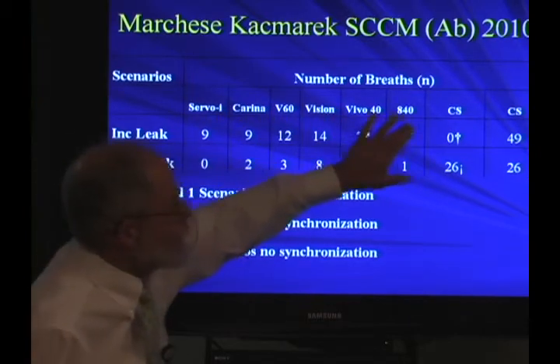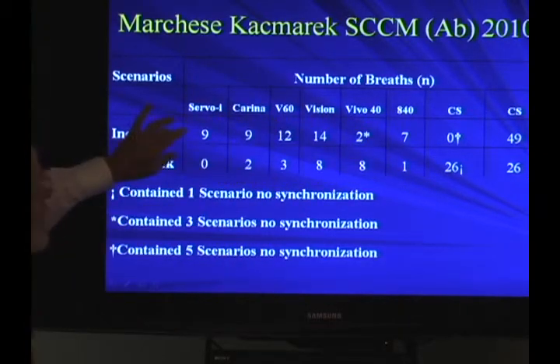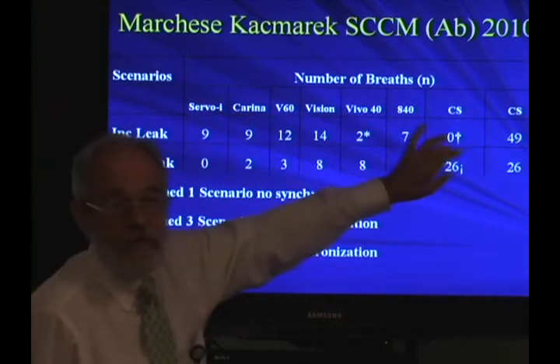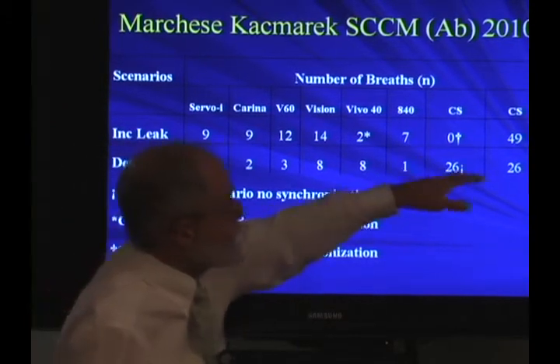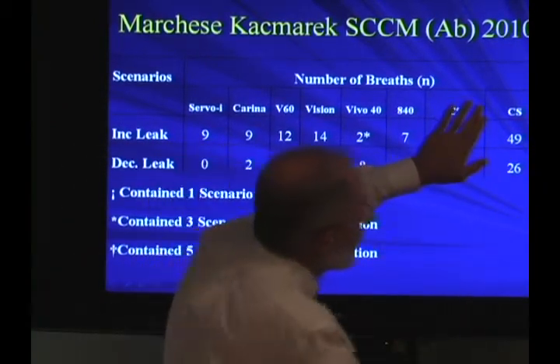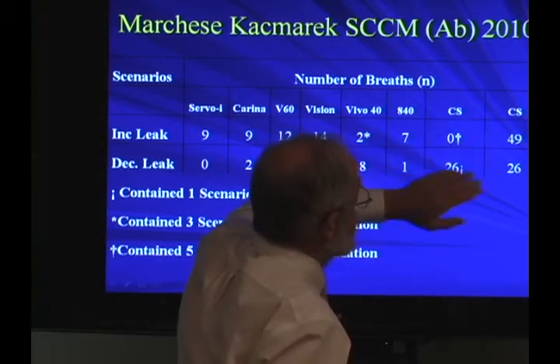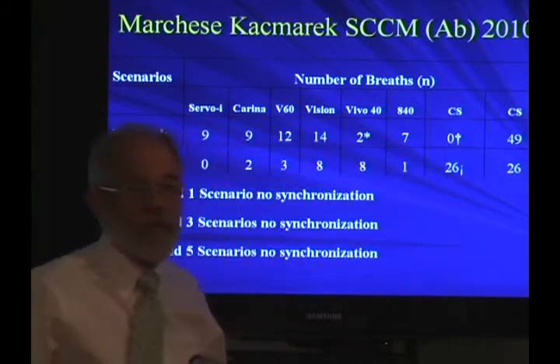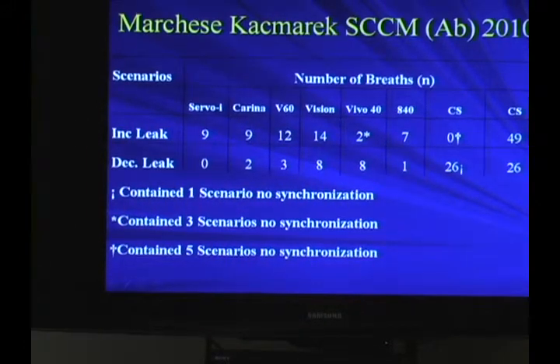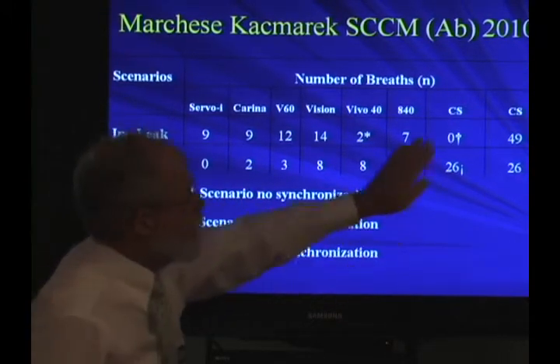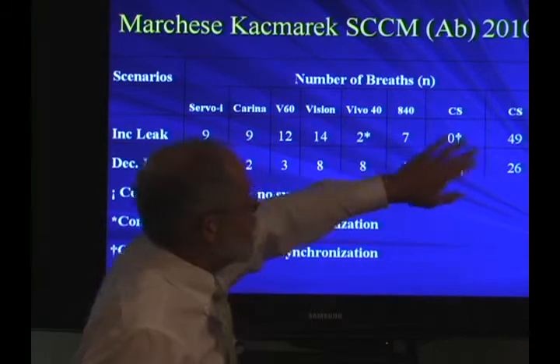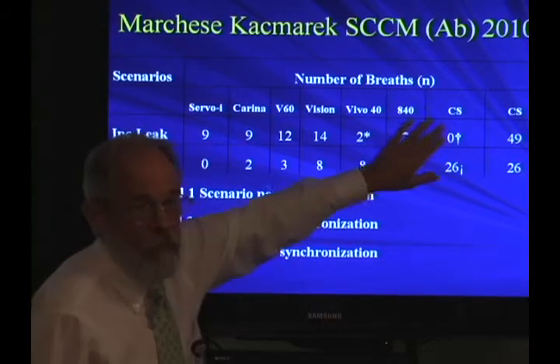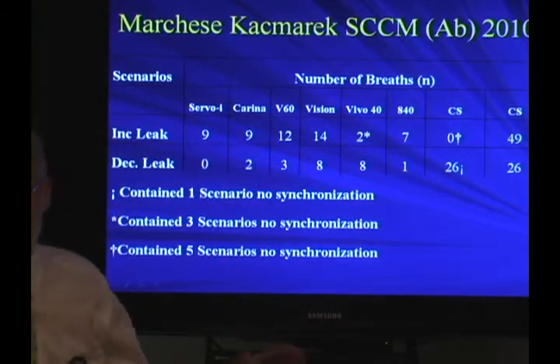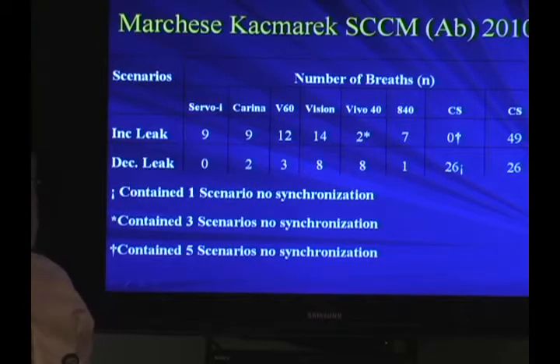It's hard to say there's really any significant difference between the function of any of these ventilators. The care station did poorly. This is without any adjustment. We went in and made some adjustments in the sensitivity and in the termination criteria, and it did better, but without doing that, it did really poorly. These we set up with baseline leak, and we didn't touch them after that, and we went up to leaks of 37 liters per minute.